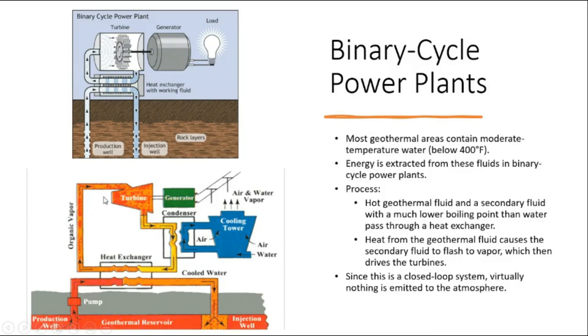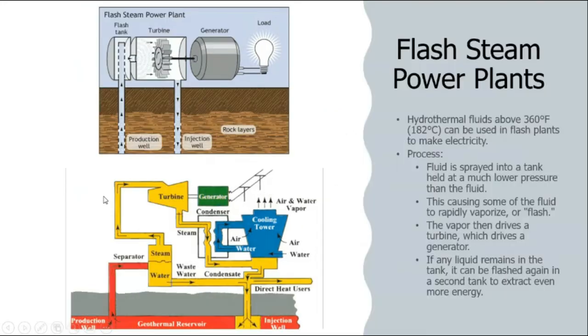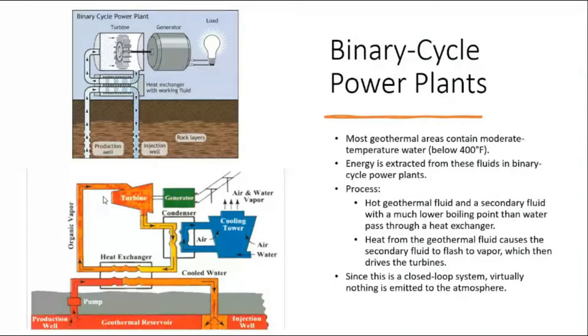Depending upon the temperatures available: if there is very high temperature, we go for dry steam power plants; at around 182 degrees Celsius, we go for flash steam power plants; and if there is lower temperature, we go for binary cycle power plants.